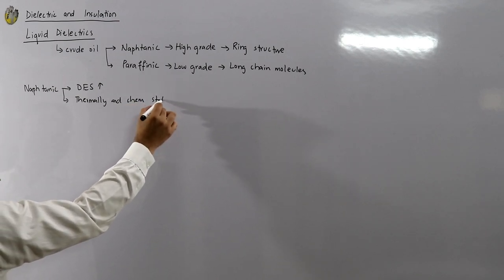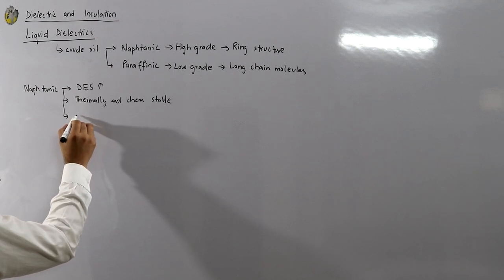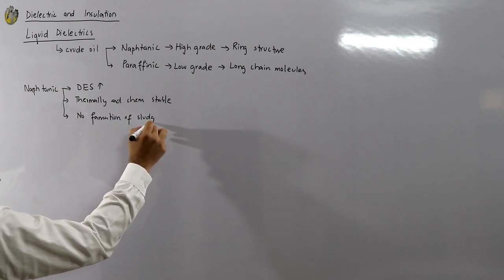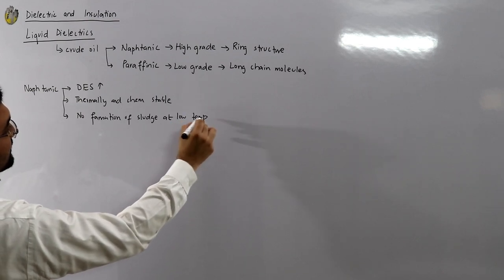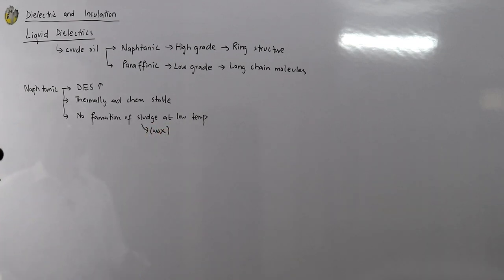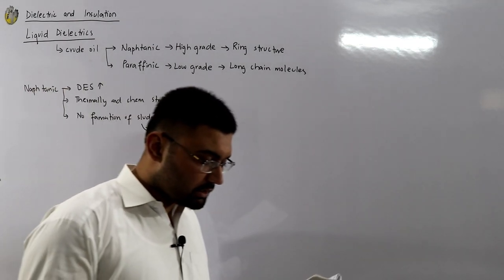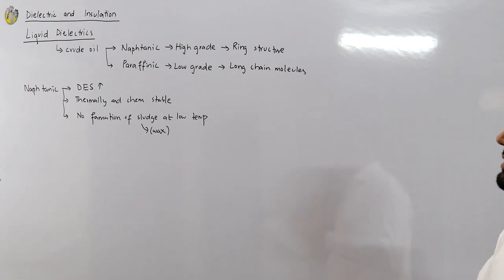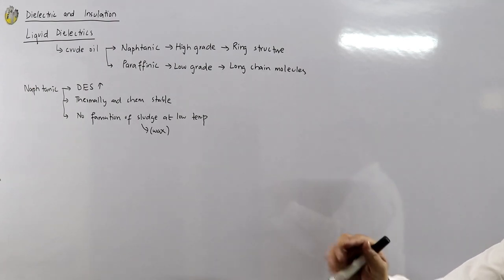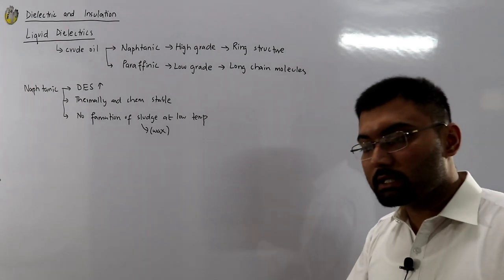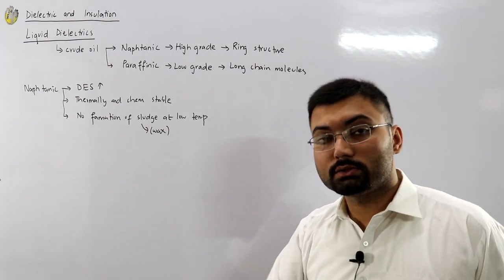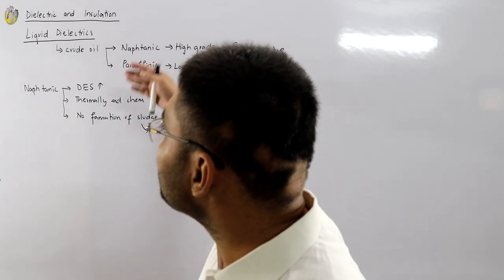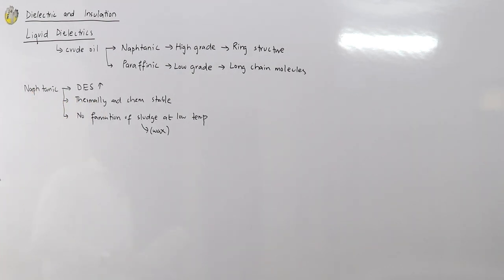Sludge is a waste material in the form of wax that settles down. In transformer oil, which circulates through radiator piping, sludge would block those pipes and affect the cooling system. Paraffinic is the low-grade oil by comparison. Both are crude oil derivatives, but naphthenic is preferred. Paraffinic is also used in some cases.